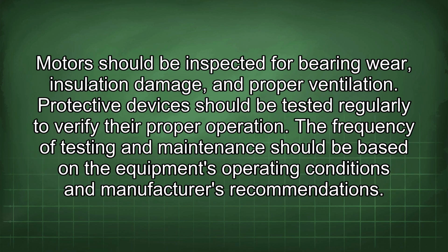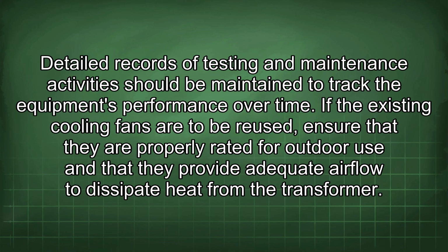Motors should be inspected for bearing wear, insulation damage, and proper ventilation. Protective devices should be tested regularly to verify their proper operation. The frequency of testing and maintenance should be based on the equipment's operating conditions and manufacturer's recommendation. Detailed records of testing and maintenance activity should be maintained to track the equipment's performance over time.